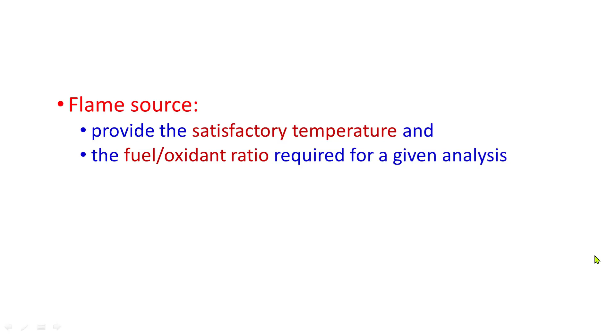Flame source provides the satisfactory temperature and the fuel oxidant ratio required for a given analysis. This table shows characteristics of common flames and their temperatures. Like air acetylene, temperature of 2300 degrees centigrade, acetylene nitrous oxide, temperature of 2800 degrees centigrade, acetylene oxygen, temperature of 3100 degrees centigrade, liquefied petroleum gas and air, temperature of 1800 degrees centigrade. Maximum operating temperature of the flame is determined by type of fuel and the oxidant. Exact flame temperature is fixed by fuel oxidant ratio.